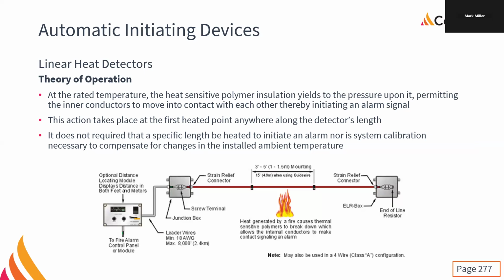And then to that, we run normal wiring out to the area, and then we put in strain relief connectors, and then we just run it to wherever we need. And at the other end, a strain relief connection and an end of line resistor. And then we have to make sure that it's mounted and supported properly. Right? It can be mounted along a messenger wire. It can just be tie wrapped to things.